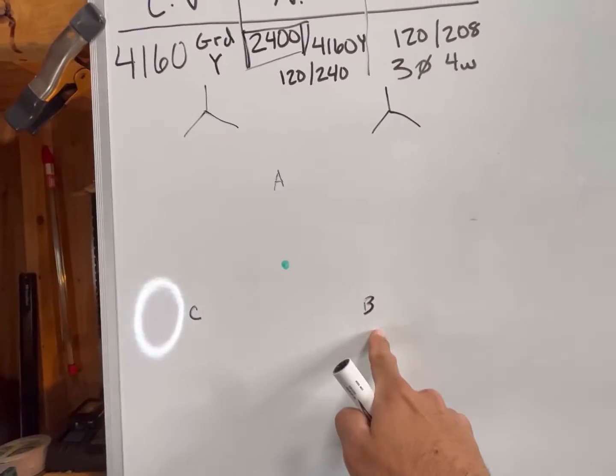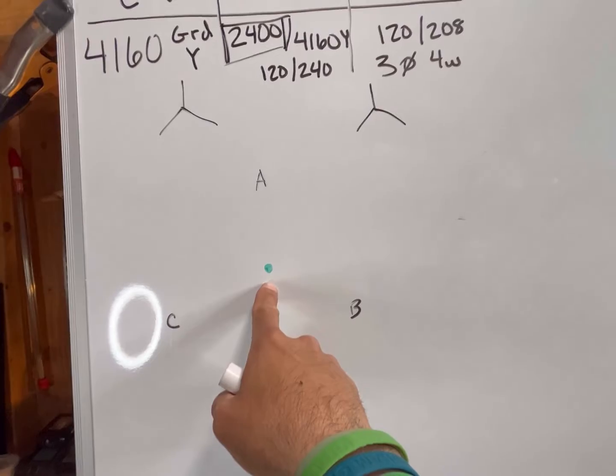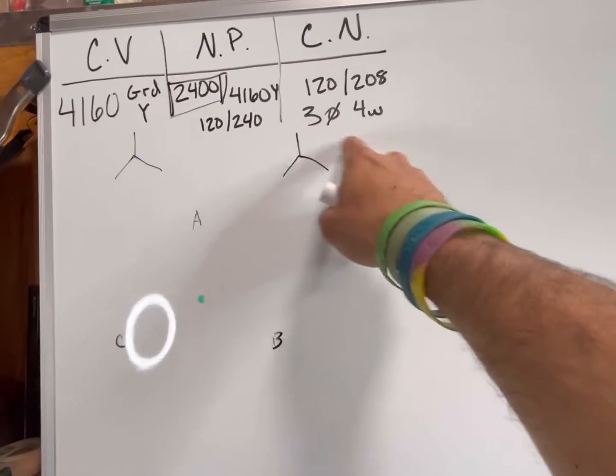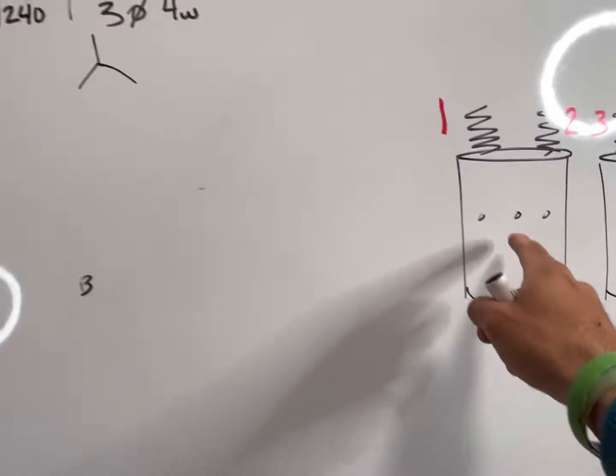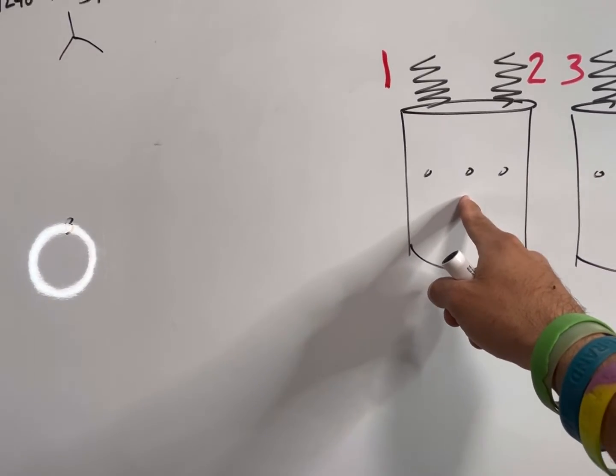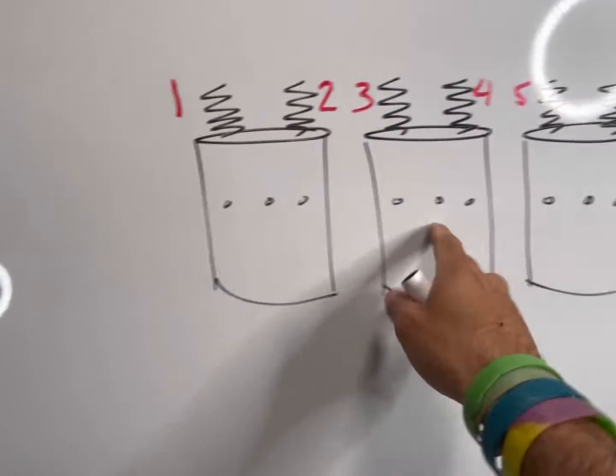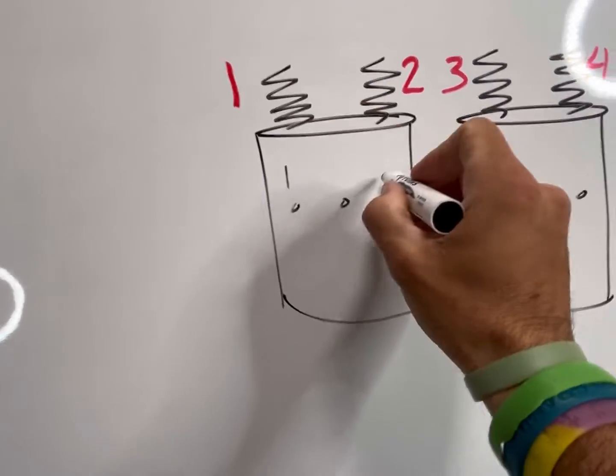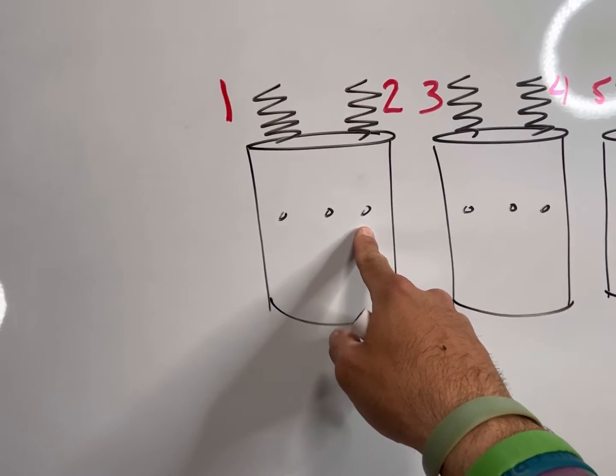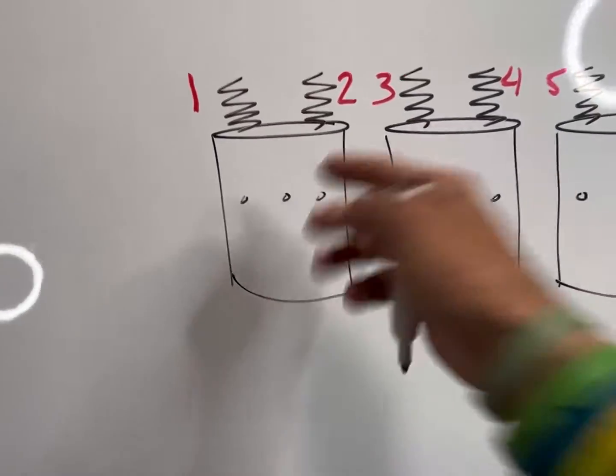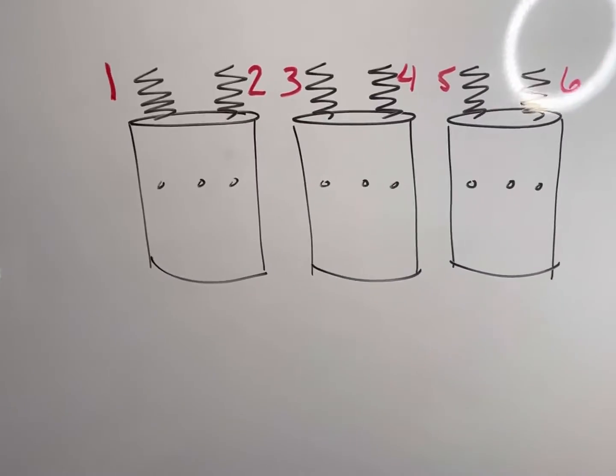I've got my primary circuit — it's a 4160 grounded Y, so A, B, and C phase with grounded neutral in the middle. With this transformer bank, a 120/240 with a 120/208 secondary hookup, I'm going to have to parallel the secondary coils of these transformers. Since I have to parallel the secondary coils, rather than having my 1 and 2 on the outside two bushings, I'm going to have to use my X1 and X2 bushings.